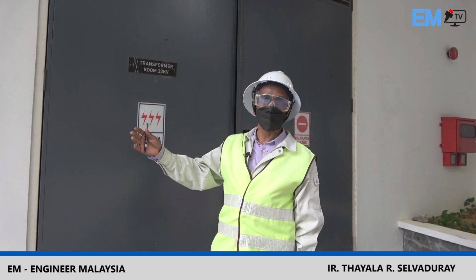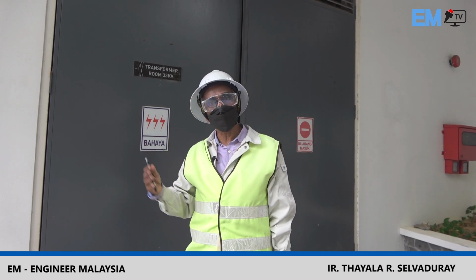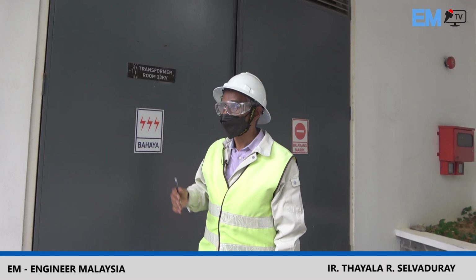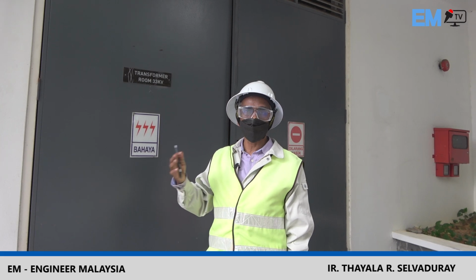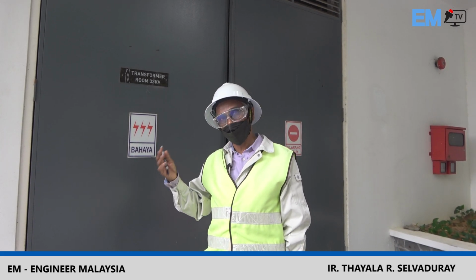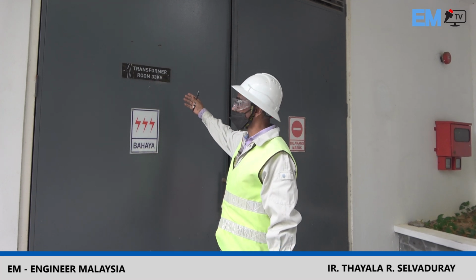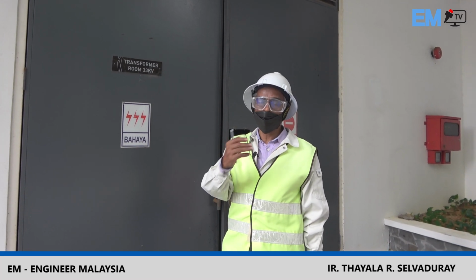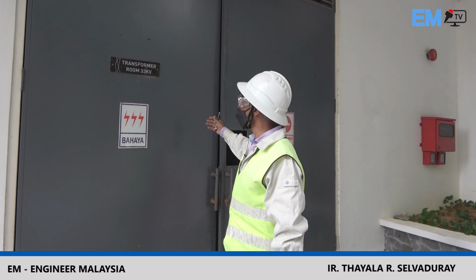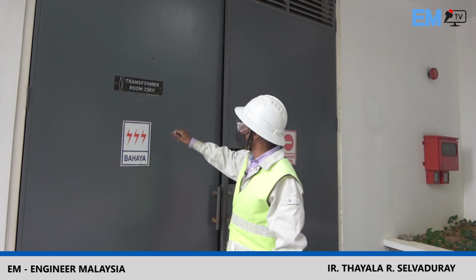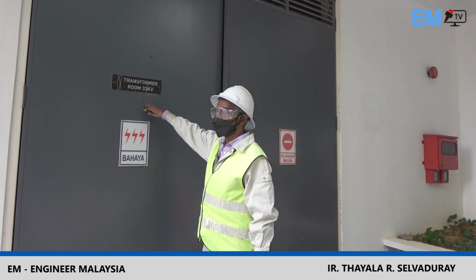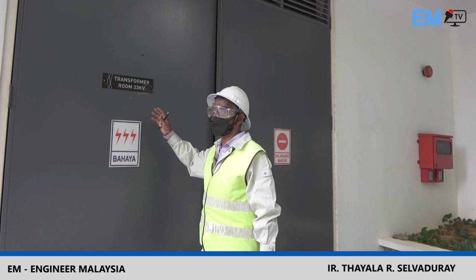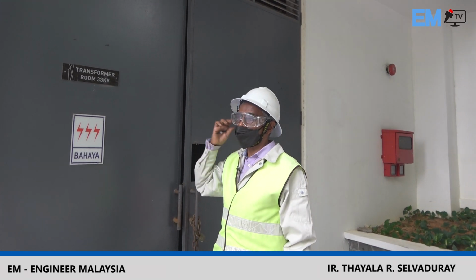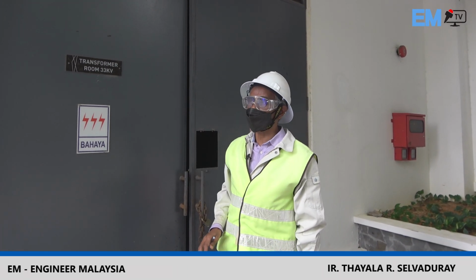Hi, what I showed you earlier was the 33 kV switchgear room. There are two incomers there. One is for the management and the other one is for the tenant. The management has two transformers. The two transformers are located inside here, and the tenant has four transformers. The four transformers are located here. The incoming is 33,000 volts and the outgoing of these transformers is 433 volts. From there they'll go to the switchboard for distribution to the respective areas.